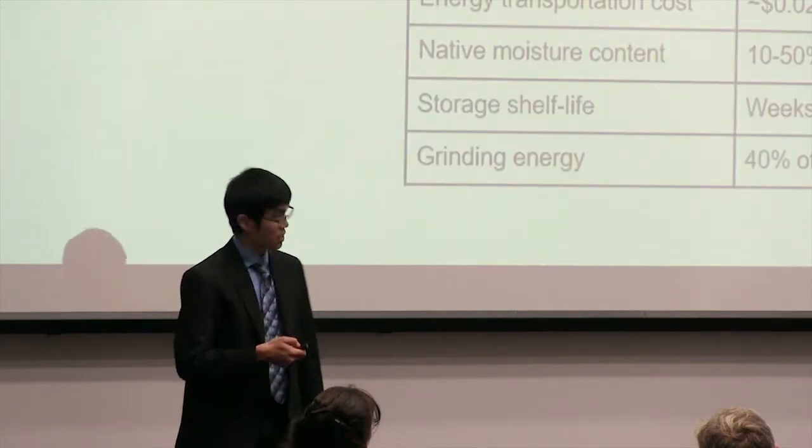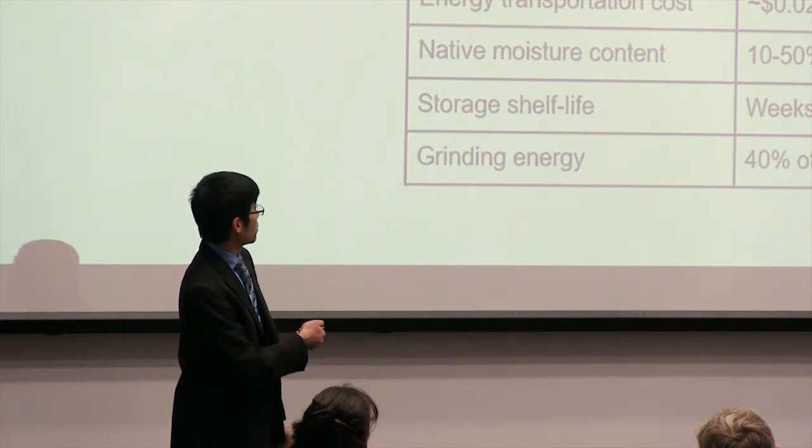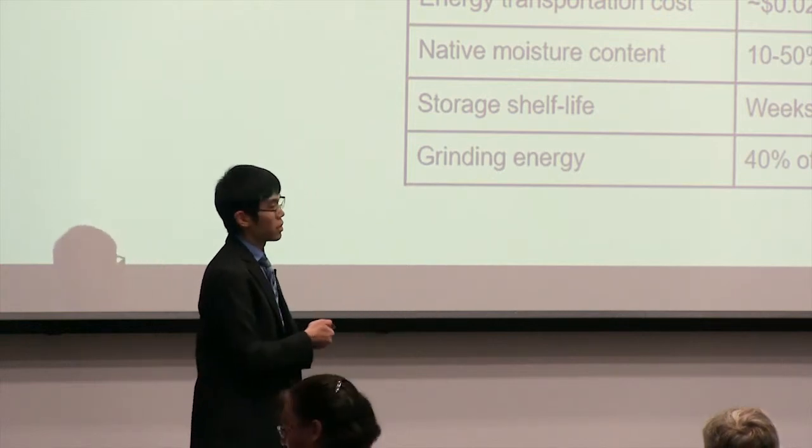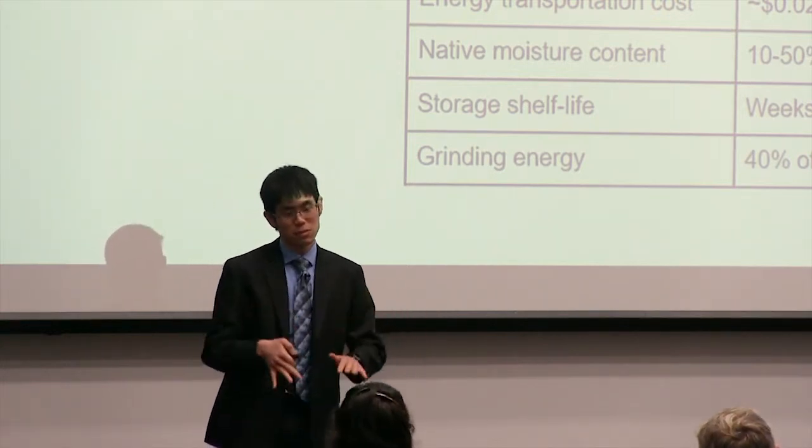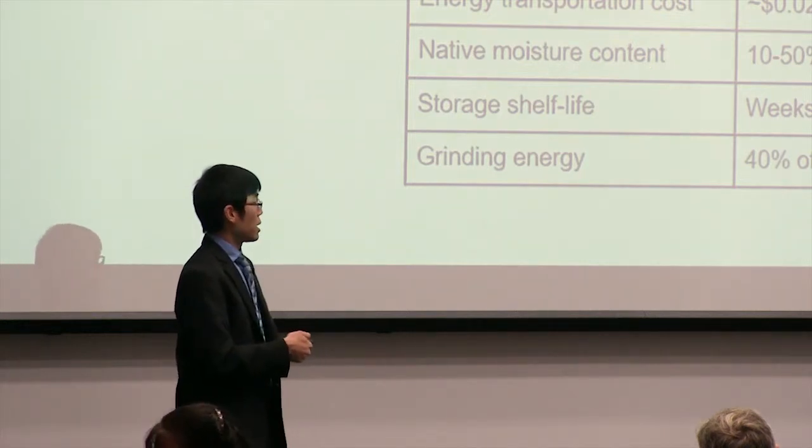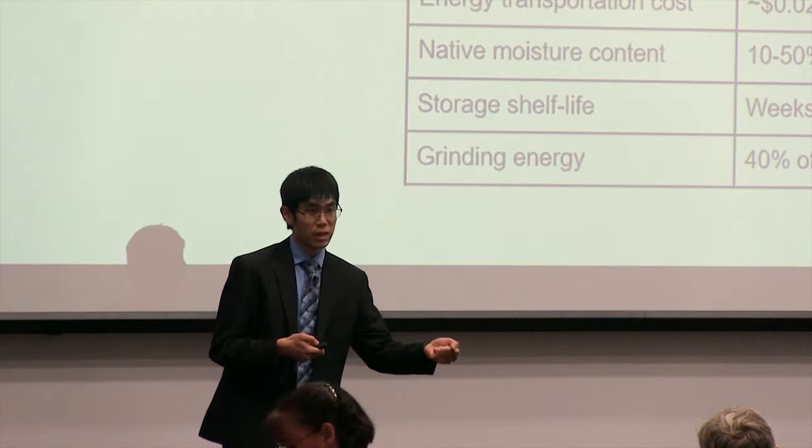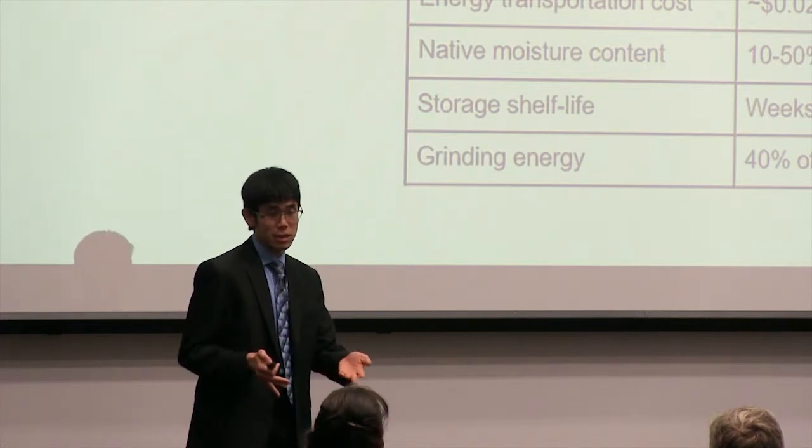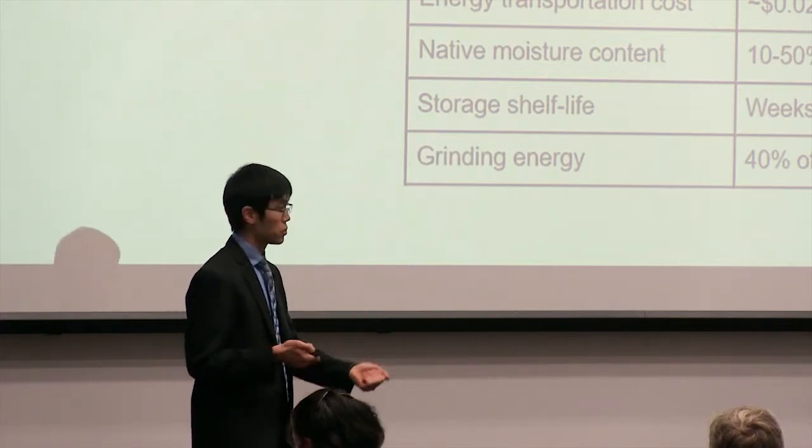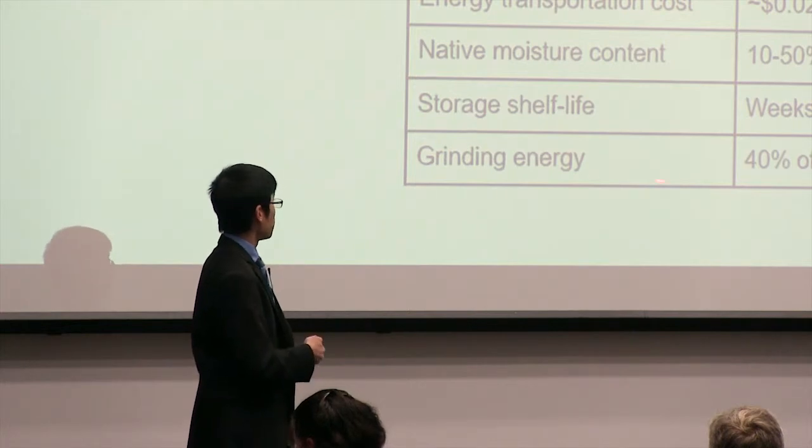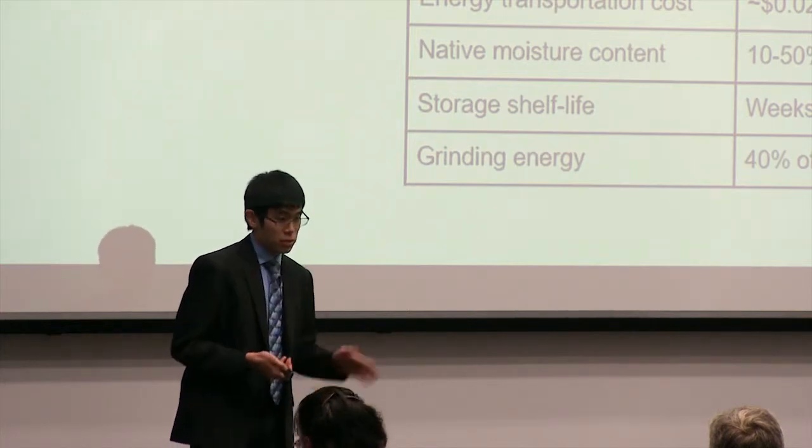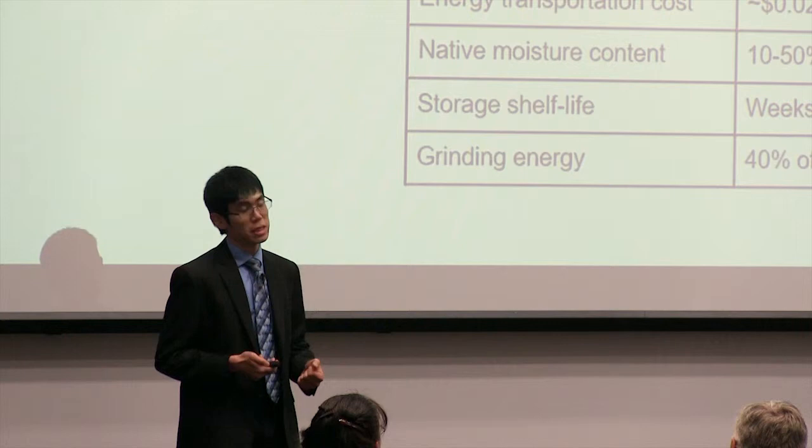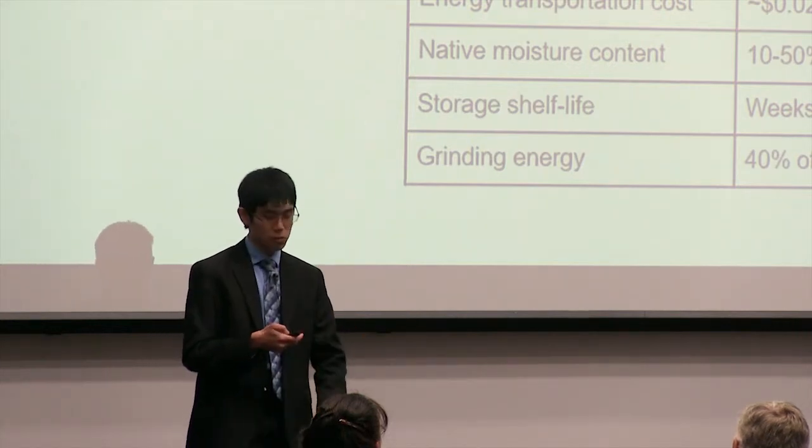The various benefits are captured in this table here. In terms of density, we can raise about five times. That means for the same truckloads, you can load a lot more energy output, and therefore, reduce transportation costs. Furthermore, torrefaction actually renders biomass hydrophobic, meaning that it's resistant against moisture attack, and therefore, greatly extends shelf life, addressing some of the reliability issues of using this sort of energy. And finally, more importantly, this process also increases the grindability of the biomass, making it much less energy-intensive to process for a form that can go into the boiler.